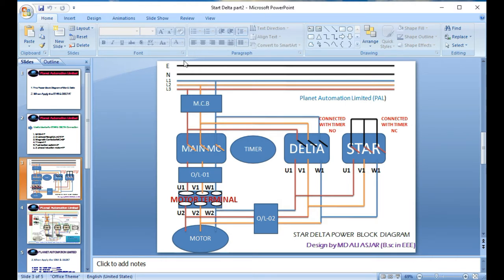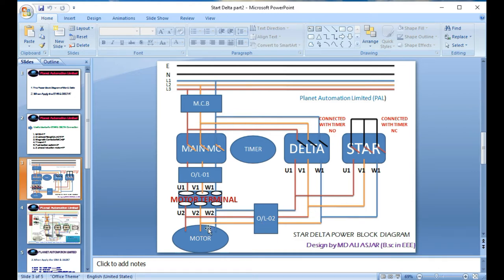Let's start the block diagram of the star-delta. There is a neutral and three-phase line. All devices are connected to the three-phase line. The push button and timer are 220V devices and are not directly connected to the three-phase line in the same way. The three-phase line goes from the MCB into the main magnetic contactor, then to the overload relay. The second magnetic contactor is the delta and the third is the star.